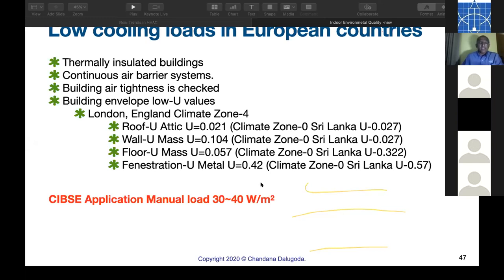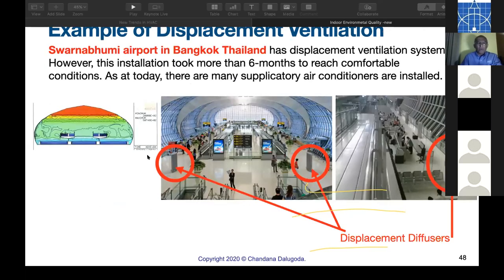That is why in the North European countries, the cooling load is low. Now, from CIBSE Application Manual 10, usually their loads are 30 to 40 watts per square meter. Those are the places good for displacement ventilation. Now, how do they achieve it in Suvarnabhumi?